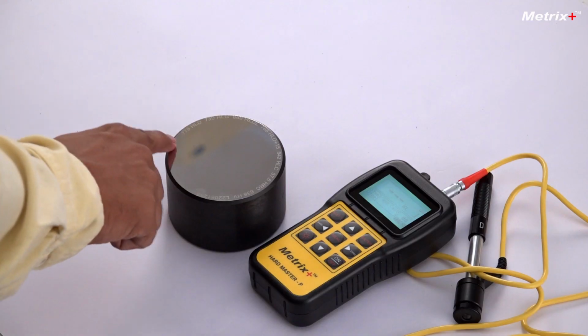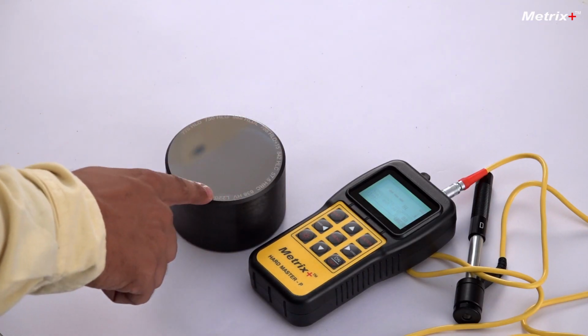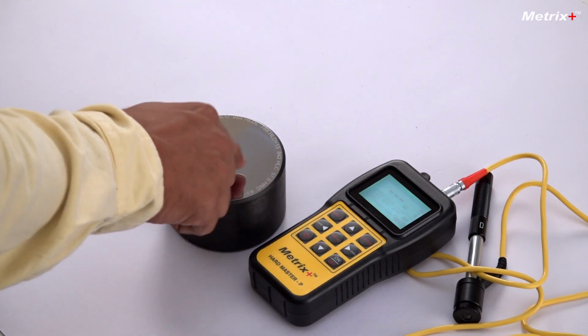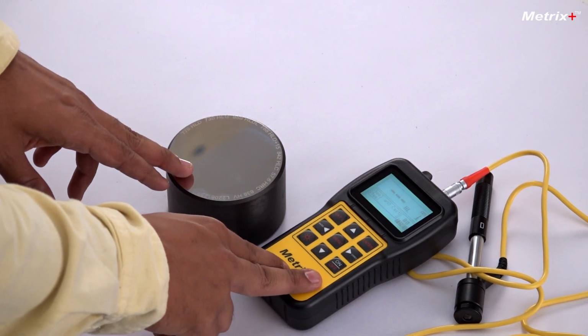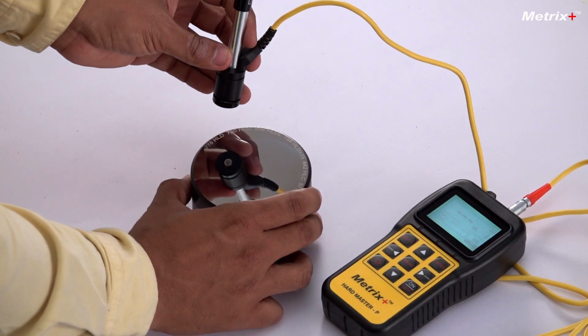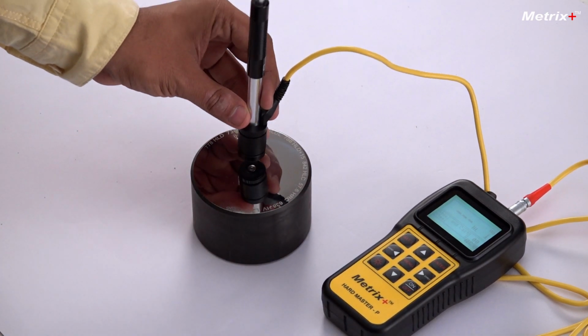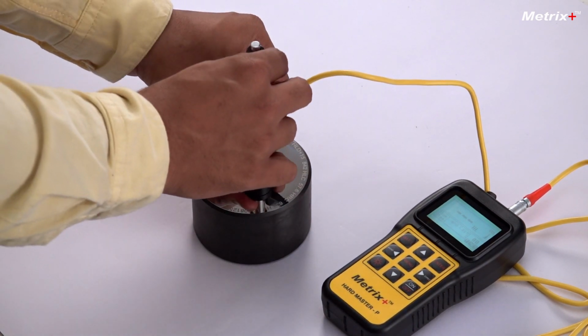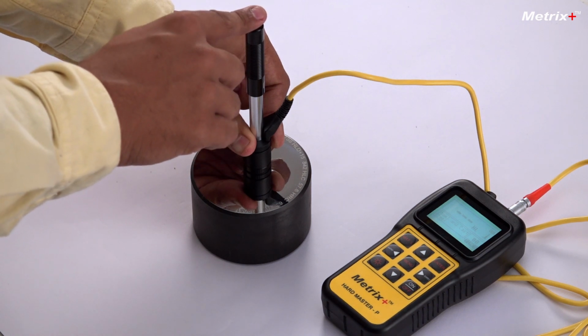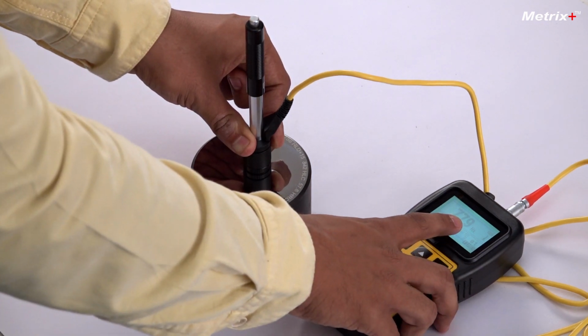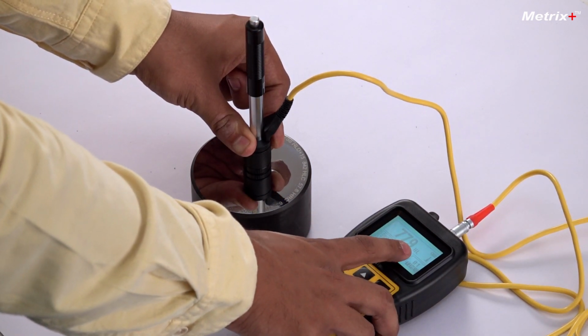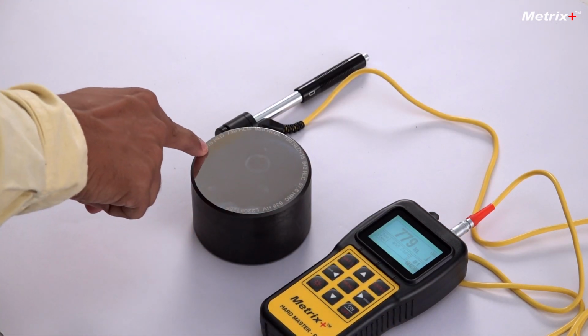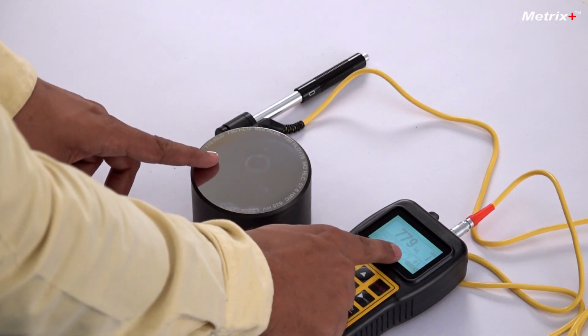We have given a standard block for calibration as well as usage. All the values of this block are written. This is made of stainless steel and the values are written to verify the meter's proper working. So first we'll measure on this. We'll keep it on the surface. We load it and then we press the trigger button. And you can see the value 779 HL is shown. This block is of 778 HLD. So this is how we verify the working.